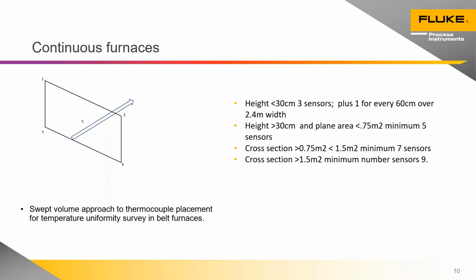Moving on to continuous furnaces, and the topic gets more complicated. So there are 2 approaches to continuous furnaces. There's either a volumetric measurement or a plane approach, a plane method or swept volume. So if you imagine the plane on the left side there, proceeding through a conveyorized furnace, thermocouples placed in the corners, 1 in the center. As it goes through the furnace from entry to exit, it will sweep through the entire volume of the furnace, taking measurements as it goes. Our recommendation is always to place the data logging system behind the survey frame, so as we don't get any shielding or shadowing from the barrier, shadowing the thermocouples.